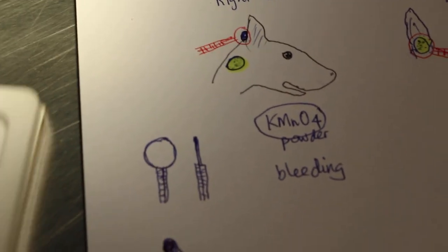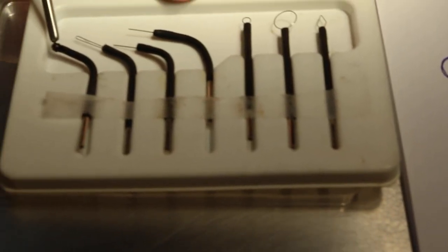Now, there is another electrode. This electrode is switched to the coagulation mode in the machine and this electrode will coagulate the blood vessel, stop the bleeding. You have to change the electrode and use this to coagulate the wound. After you remove the wound, you take out this one and then you go and burn the blood vessels. So, know how to use your equipment for electrosurgery.